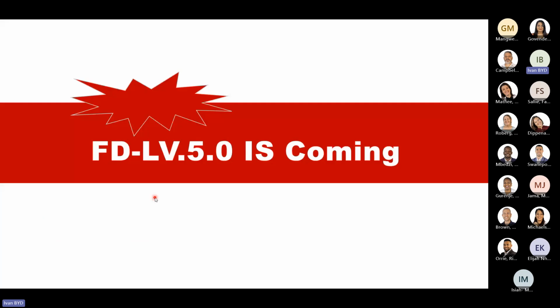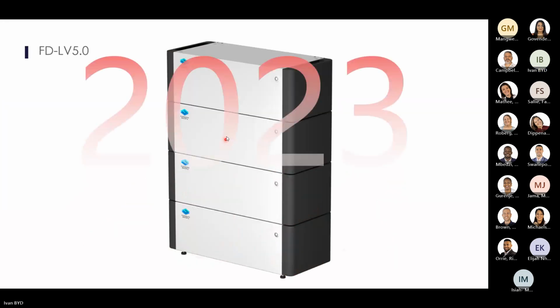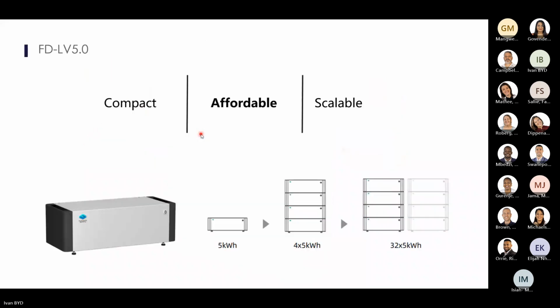And now we've got the new and interesting addition to the family. It's called the FinDreams battery. It's a 5 kilowatt hour battery that's going to be available very soon. You can stack them 4 high. It is a very similar shape to the LVS, but with external wiring. It's not the internal wiring of the LVS. It's 5 kilowatt hours per module, and you can put in parallel 32 of those, which is 160 kilowatt hours.